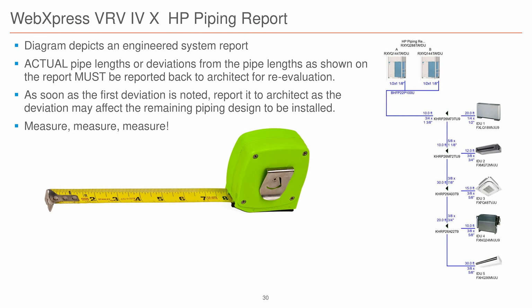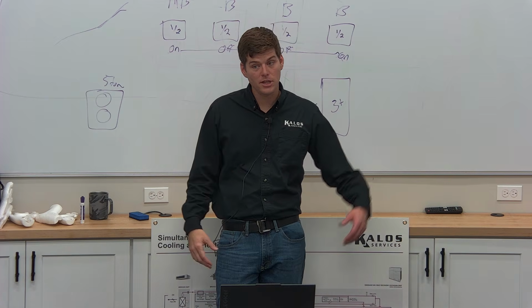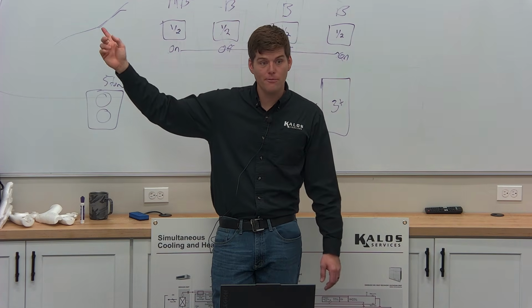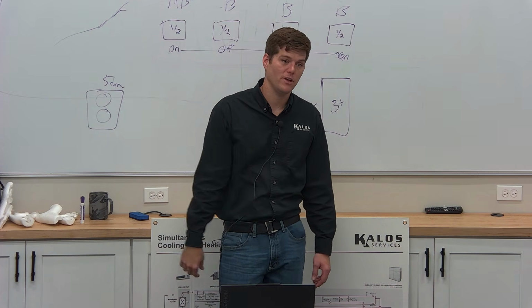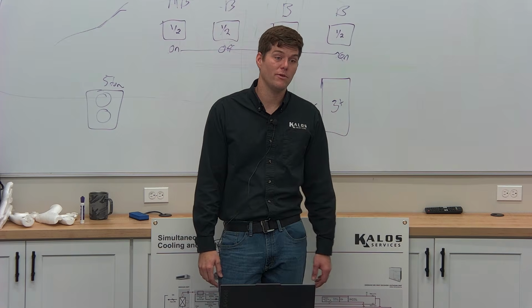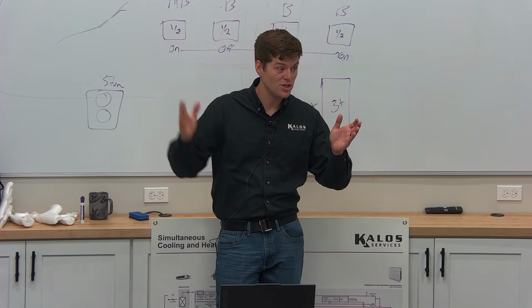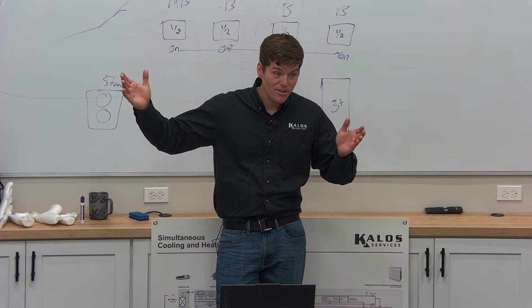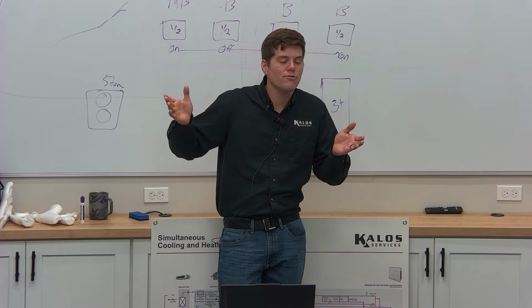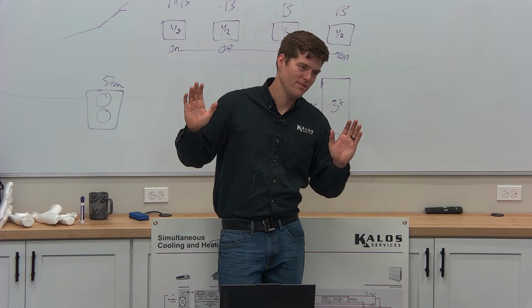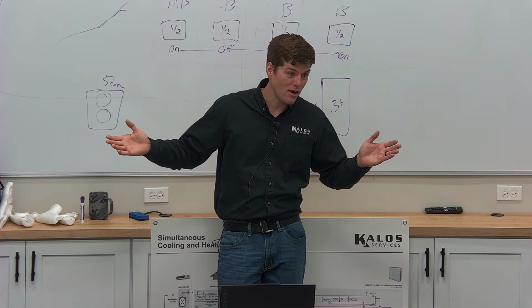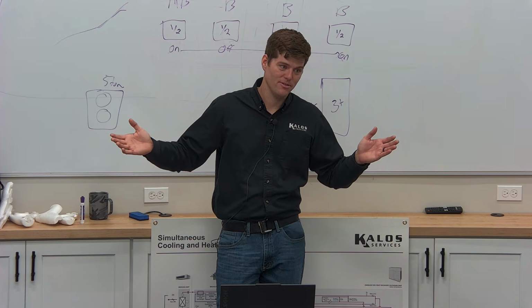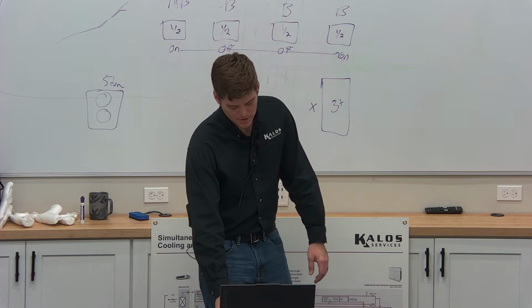Installation, recording distances, ensuring your line size is correct. If you have to completely relocate a unit, it has to go through this program first before you install it and say, yes, let's put it there, because you might find out the suction line went from 7/8 to 1 1/8. That's a big deal. Sure, 3 feet, not that big of a deal. 75 feet up through a riser to a roof, that's a very big deal. And that's where people usually miss the mark, right?